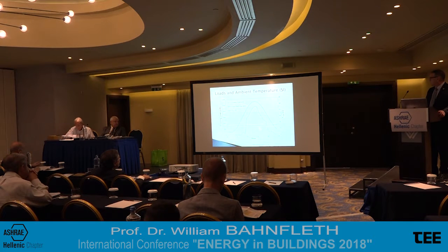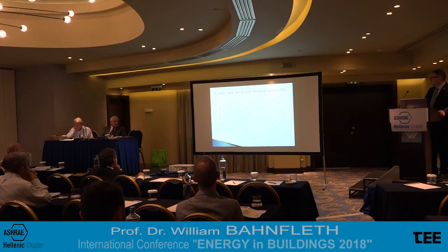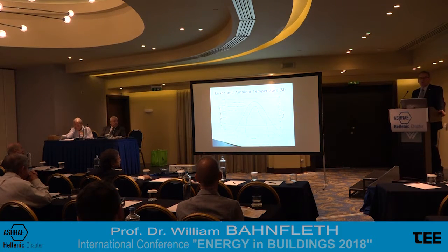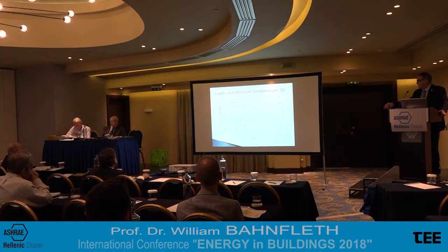And if I were to take all of the load represented by that curve and average it out, it would give us a plant that was sized according to this horizontal level load curve. And the other curve on this plot is the air temperature. So you can see that the highest loads on my load profile occur when the outdoor air temperature is the hottest, so we would expect that we would have the lowest COP for the cooling plant at that time. And if I can take all of this cooling load that we need to make above the plant capacity and move it over to nighttime when the condensing conditions are lower, then we're going to get some savings.